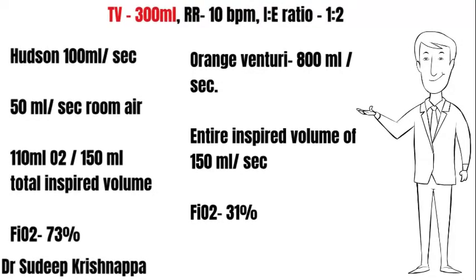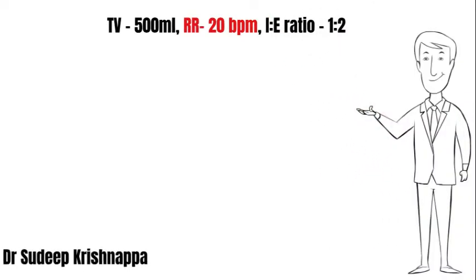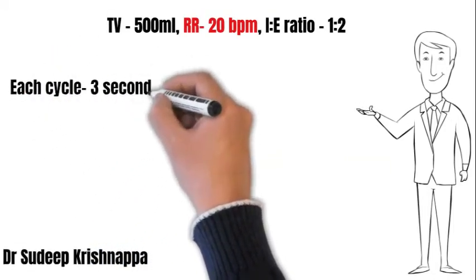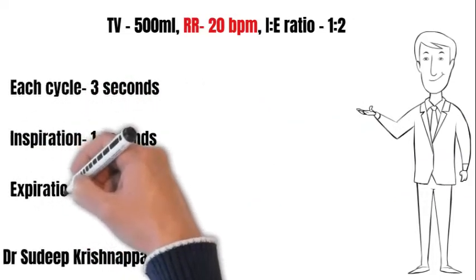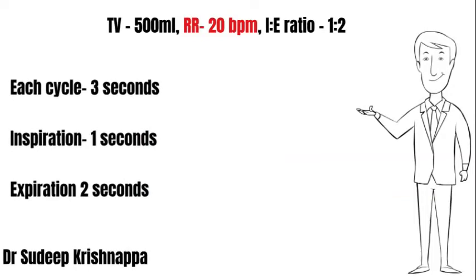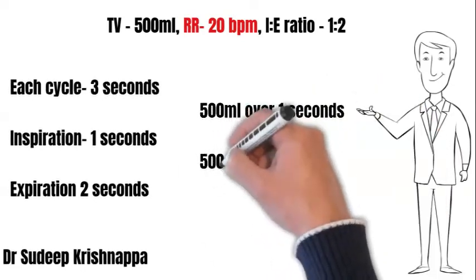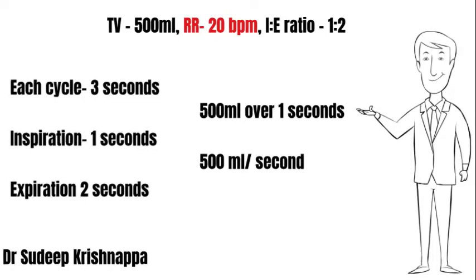Moving to the next scenario: we keep tidal volume at 500 mL but change the respiratory rate from 10 to 20 breaths per minute, keeping the I:E ratio at 1:2. Each cycle drops from 6 seconds to 3 seconds. With I:E ratio of 1:2, the 3 seconds splits to an inspiratory duration of 1 second and expiratory duration of 2 seconds. The tidal volume of 500 mL now must be breathed in over 1 second, giving a flow rate of 500 mL per second.